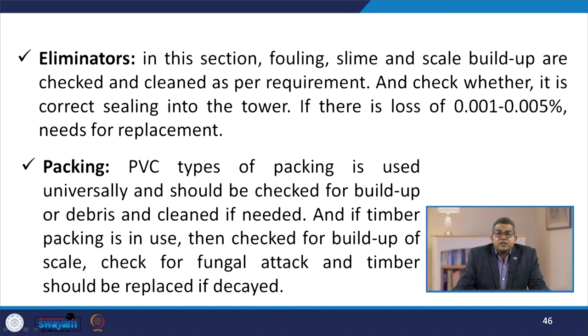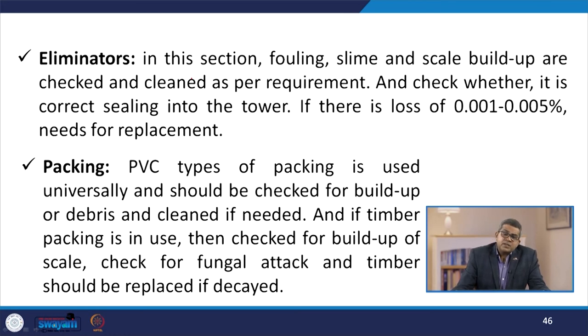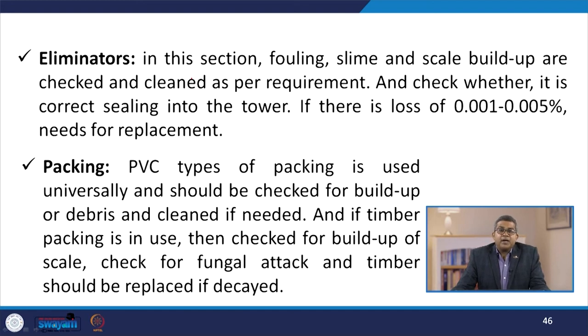Eliminators: fouling, slime, and scale buildup should be checked and cleaned as required, and it should be verified that they are correctly sealed into the tower. If there is a loss of 0.001 to 0.005%, replacement is needed. Packing plays a very vital role in cooling tower operation. PVC packing is the most commonly used type and should be checked for buildup of any debris and cleaned if needed. Timber packing should be checked for scale buildup and any kind of fungal attack or formation, and should be replaced if decayed.